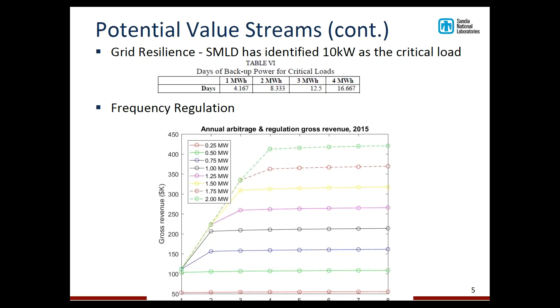But pretty much the knee in the curve always occurs when the power rating is 1/2 the capacity rating. And that's because you want to hang out at a 50% state of charge and be able to provide regulation up and regulation down. So for example, a 4 megawatt hour system with a 2 megawatt power rating can hang out at 50% state of charge and provide the full 2 megawatts up or 2 megawatts down for the full hour. So there's a knee in the curve on the top line, which is a green dotted line with the circles. But back to the more realistic size, I'm sorry, a 1 megawatt, 2 megawatt hour system can provide about $200K of annual revenue. So this is another potentially significant revenue source.